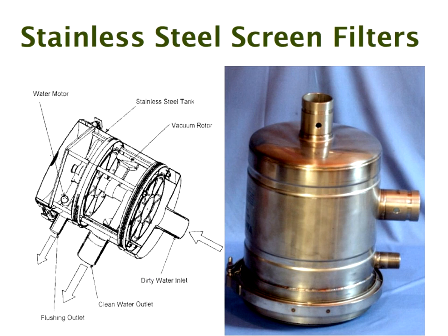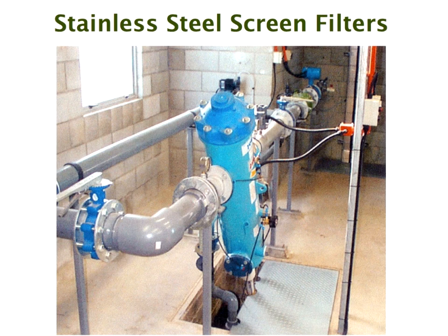They work very well. This is a stainless steel screen filter. Very expensive, automatic self-cleaning, very efficient, very difficult to take apart to maintain. It's a real pain taking it apart to maintain it. But otherwise, it's a great filter. This is the trouble. There's always a condition on everything I say.